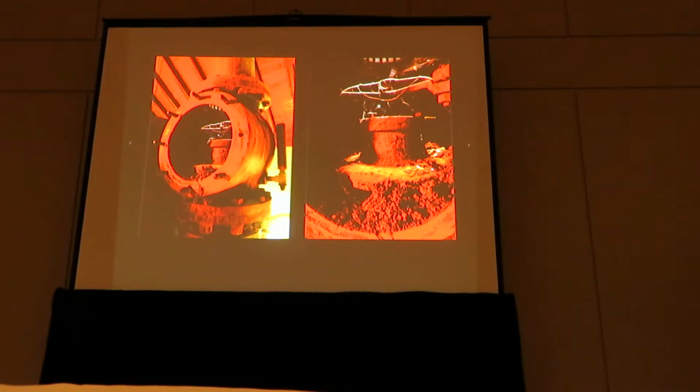The engine was in essentially working order, except for a few minor details, one of which was the atmospheric valve. This valve is on the exhaust end of the engine, and with a large engine, especially one like this, there is usually a condenser on the end of it, which collapses the steam back into water after it's gone through the machine and been used. And this does two things. It enables you to get your water back to go back to the boiler room in an endless cycle. And another more important feature is that the collapsing of the steam into water in a closed space produces a significant vacuum. This helps draw the exhaust steam out of the engine and make it more powerful as well as more thermodynamically efficient.